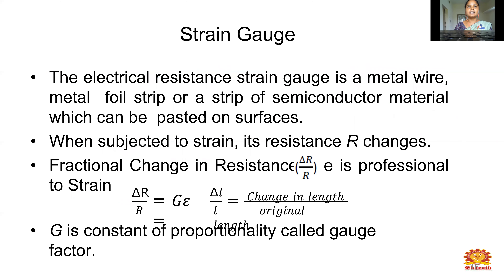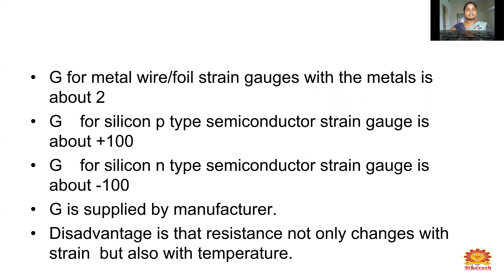Next is the strain gauge. What is meant by strain gauge? The electrical resistance strain gauge is a metal wire, metal foil strip, or a strip of semiconductor material which can be bonded onto a surface. When subjected to strain, its resistance R changes. The fractional change in resistance delta-R divided by R is proportional to strain, expressed as delta-R by R equals G times epsilon, where epsilon is delta-L divided by L — change in length divided by original length. G is a constant of proportionality called the gauge factor. G for metal wire or foil strain gauges is about 2; G for silicon P-type semiconductor strain gauges is about plus 100; G for silicon N-type semiconductor is about minus 100. G is supplied by the manufacturer.